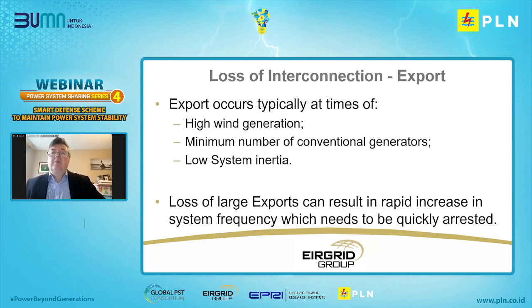Exports on our system on the interconnectors typically occur at times of high wind generation. So we have a minimum number of conventional plant on, we've got low system inertia, and the loss of large exports can result in a rapid increase in system frequency, which quickly needs to be arrested. So next slide, please.